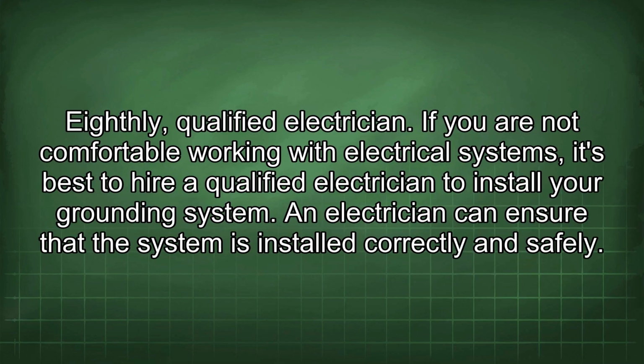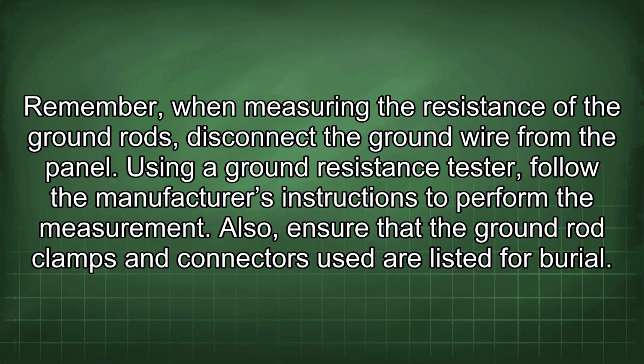Eighthly, qualified electrician. If you are not comfortable working with electrical systems, it's best to hire a qualified electrician to install your grounding system. An electrician can ensure that the system is installed correctly and safely. Remember, when measuring the resistance of the ground rods, disconnect the ground wire from the panel. Using a ground resistance tester, follow the manufacturer's instructions to perform the measurement.